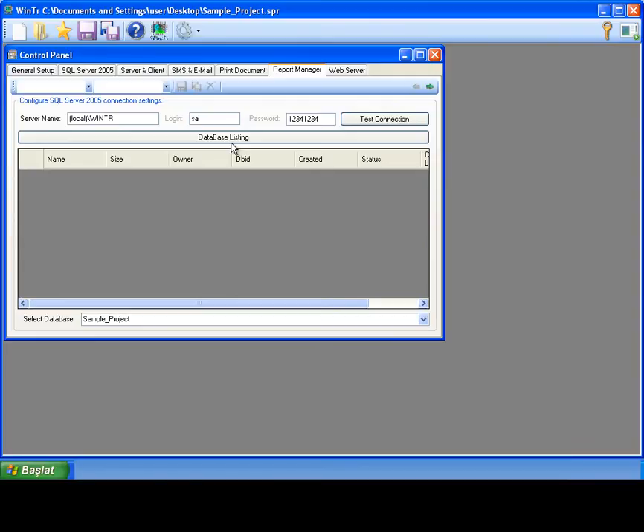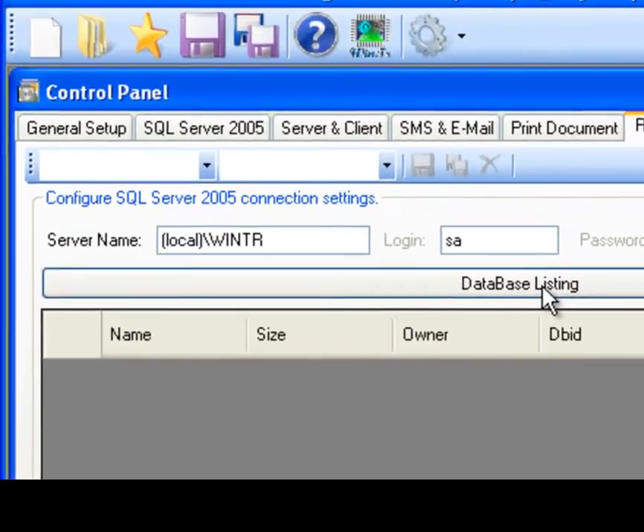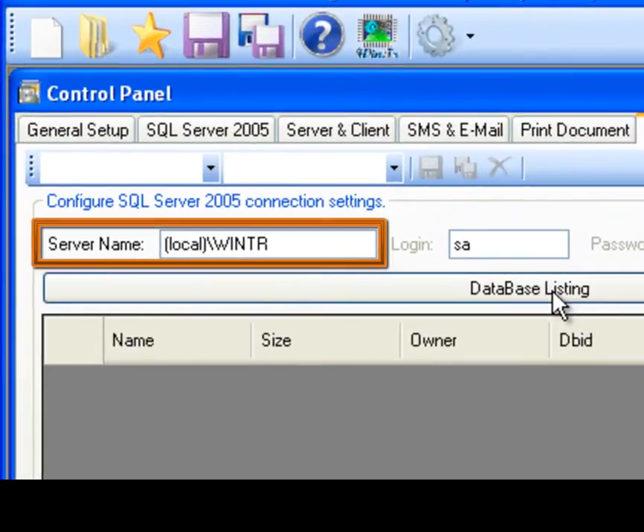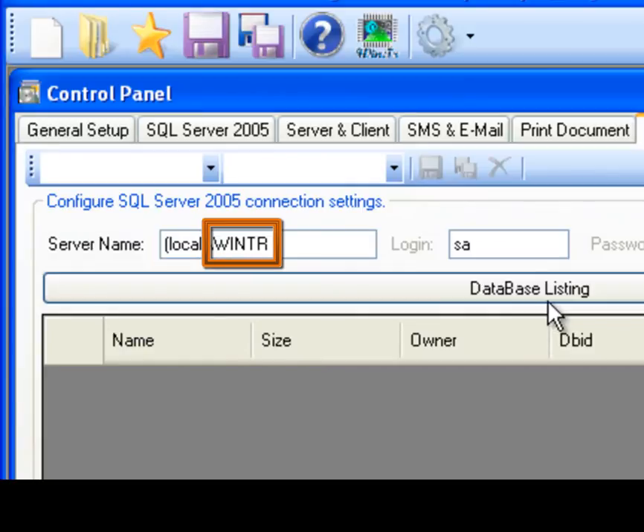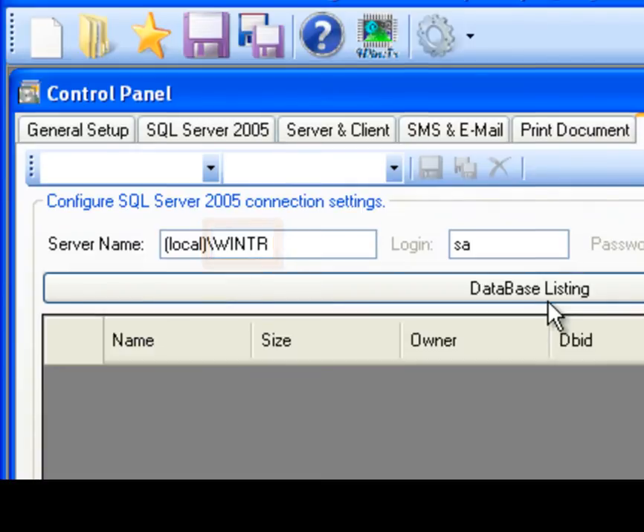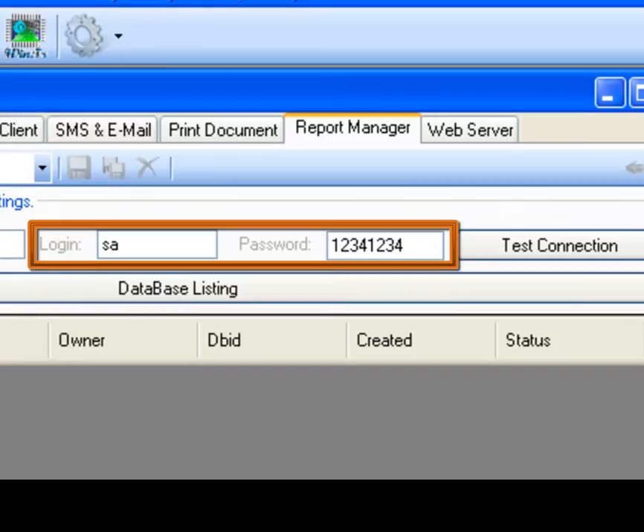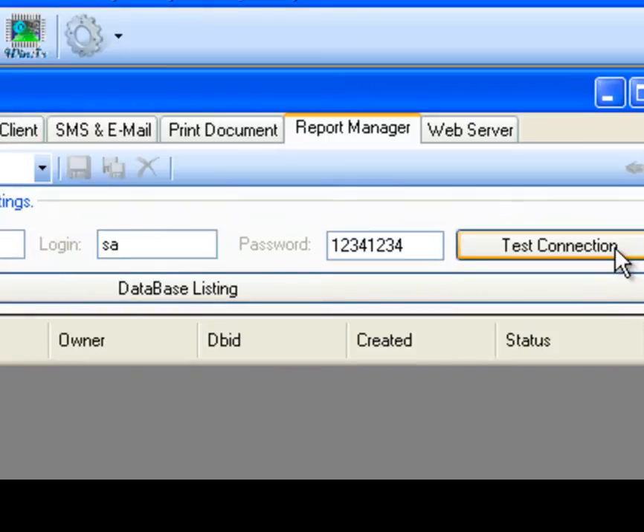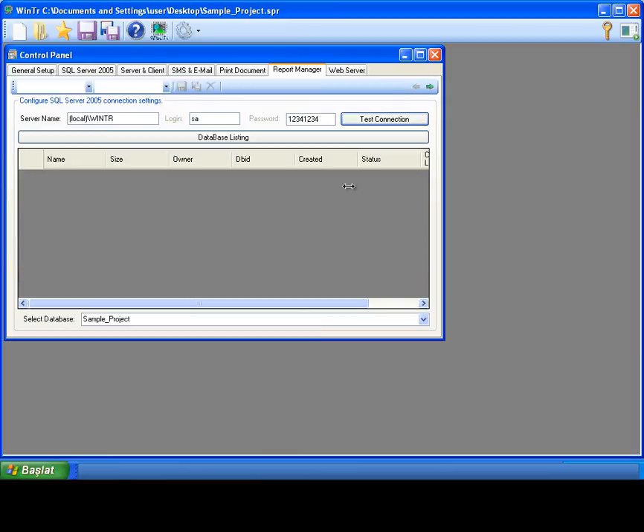The first property we talk about is server name field. Server name field is for specifying address and instance name for connected SQL Server. The local here is the address of the SQL Server on the network. This could be any IP address as well. And the WinTR is the instance name of the connected SQL Server. Because of more than one SQL Server can be installed in single machine, we must provide the instance name for connecting specific SQL Server. WinTR SCADA installs SQL Server with same name itself. So we write here WinTR as an instance name. And we must provide the username and password for connecting SQL Server. These are default username and password. And I'm confirming these parameters by clicking test connection.